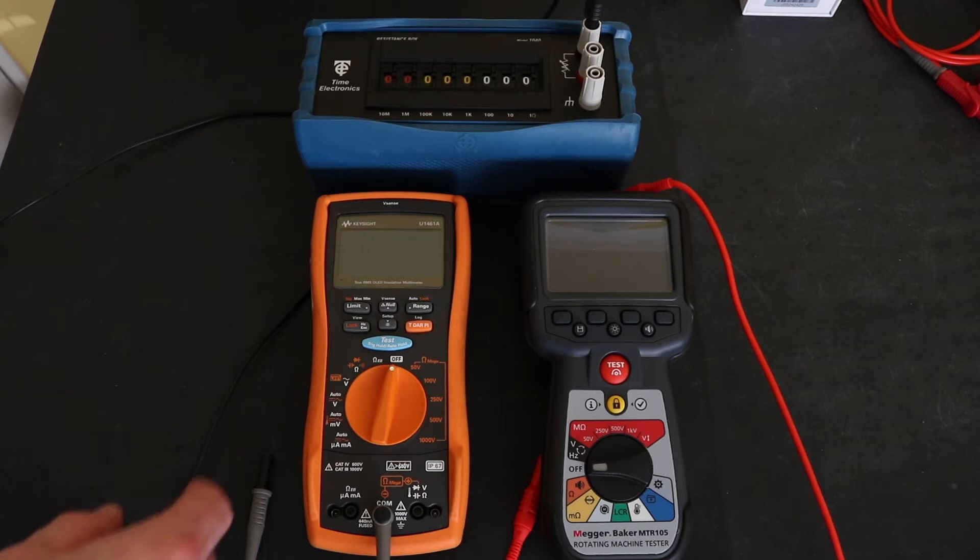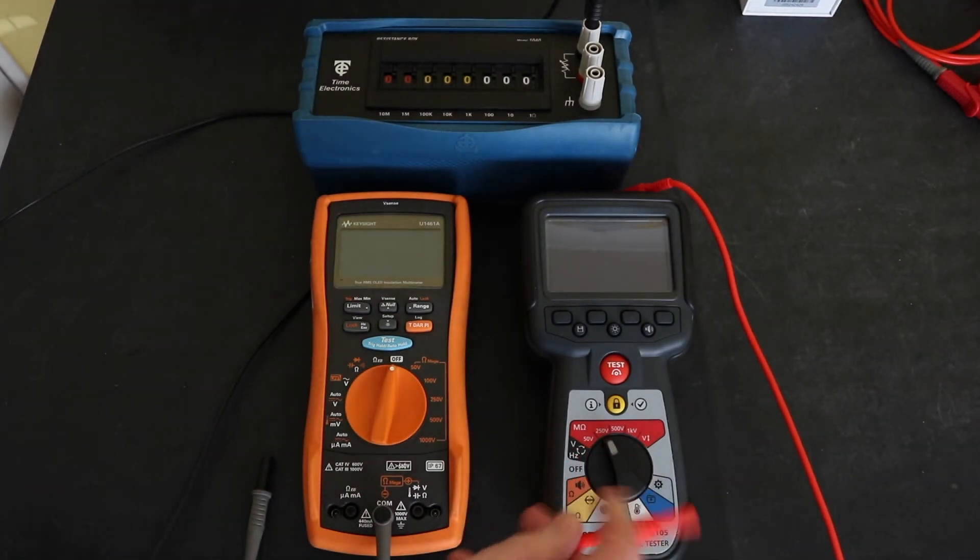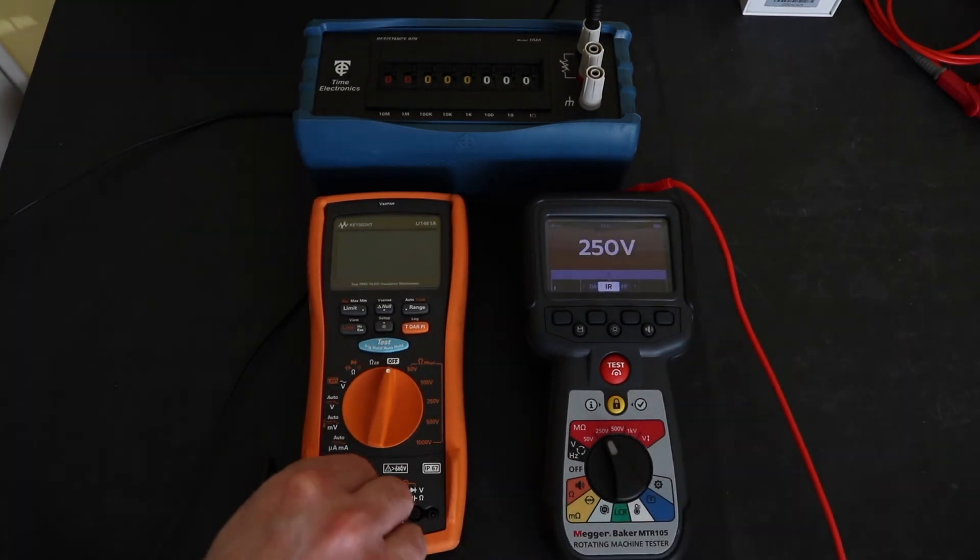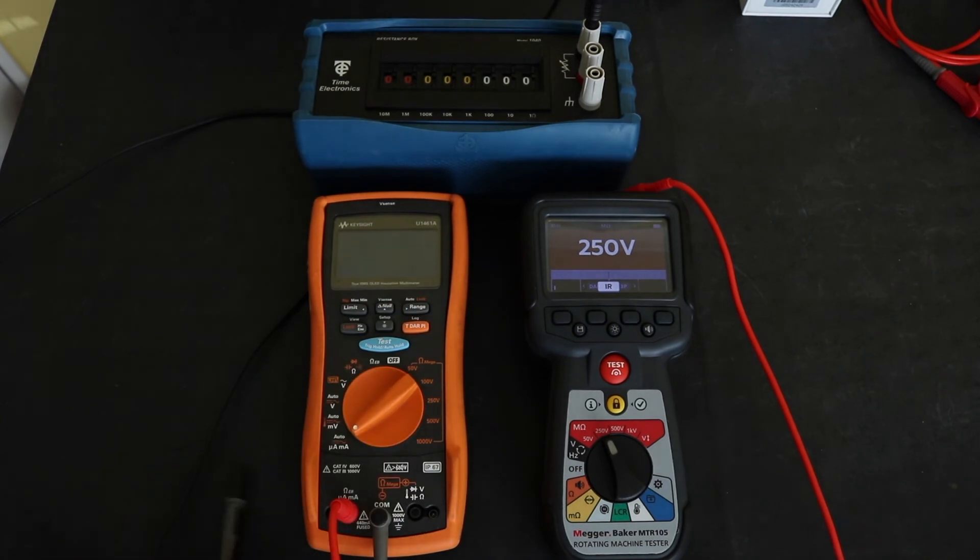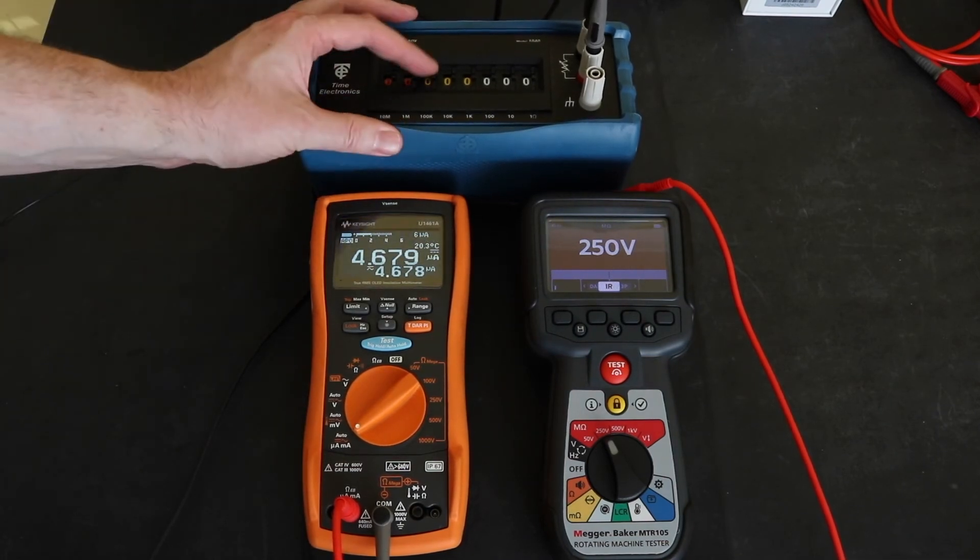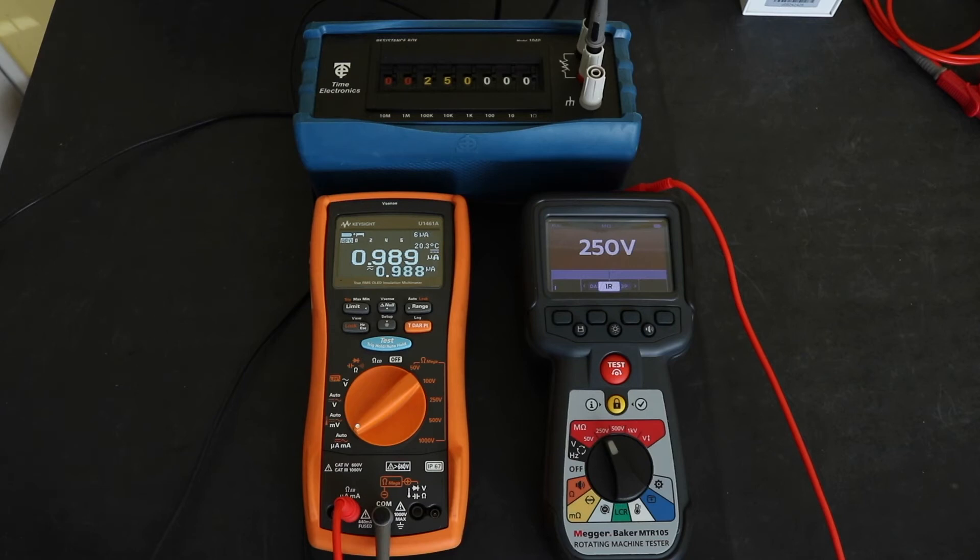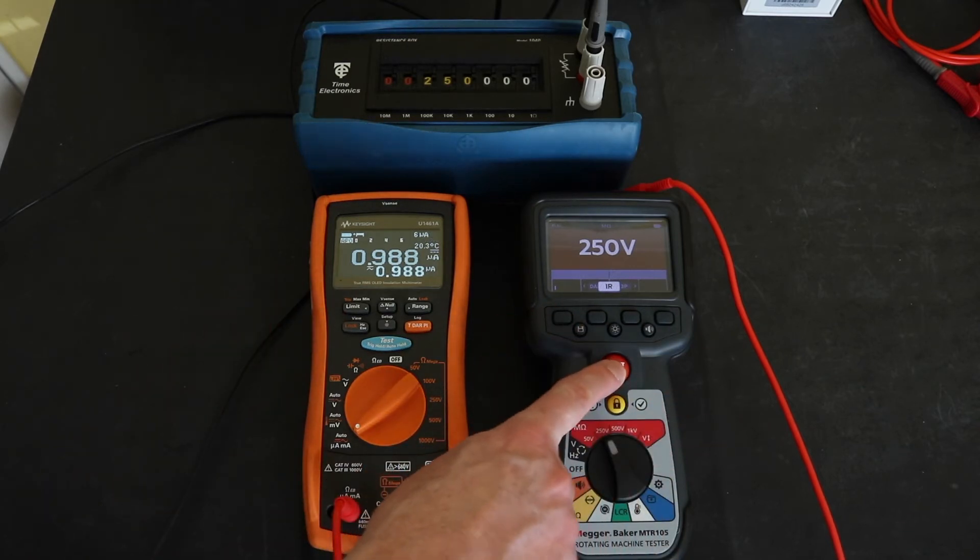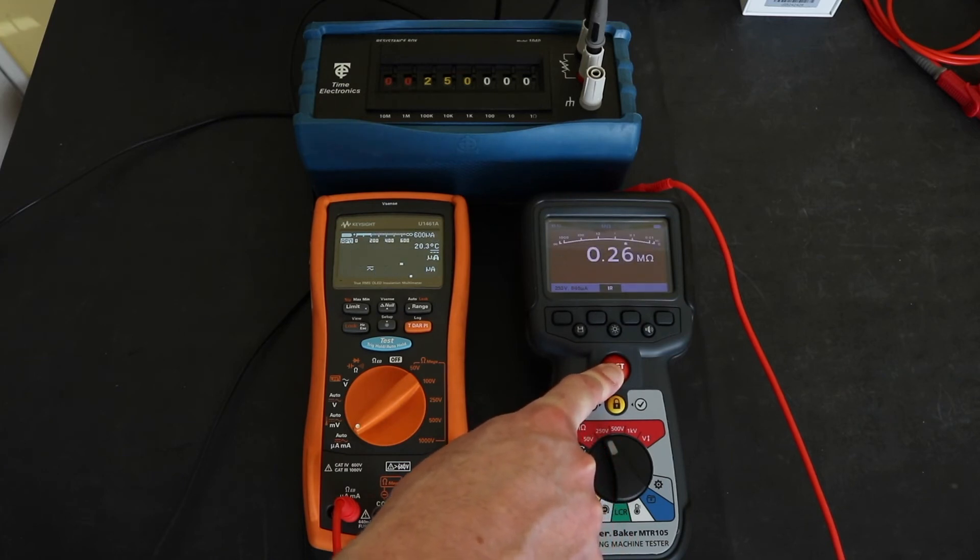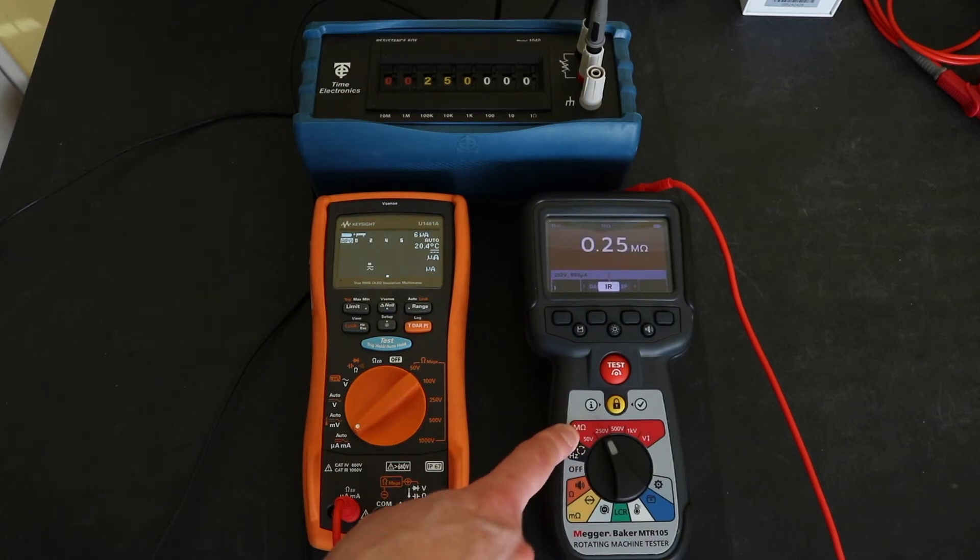So briefly, the setup to measure the one milliamp load test on an insulation tester: you have the tester set to insulation mode, I have one lead that comes out and goes to the U1461A that I'm going to use as an ammeter and then the other lead from the ammeter comes out and just goes to this resistance decade box that I will set up. So for 250 volts that's going to be set to 250 kilo ohms, set to DC, set to IR mode. So if I hit the test button you can see I've got a resistance of 0.25 mega ohms or 250 kilo ohms and there's my 1.0005 milliamps on the instrument.